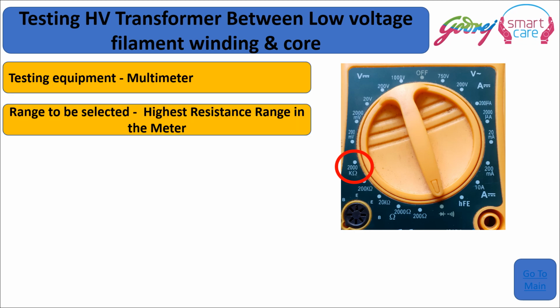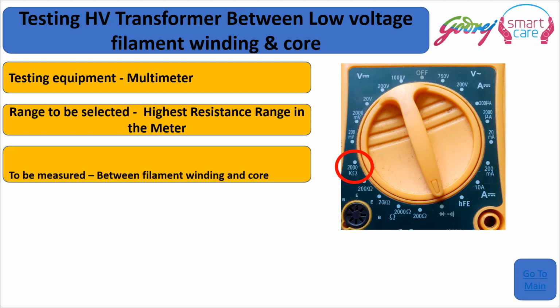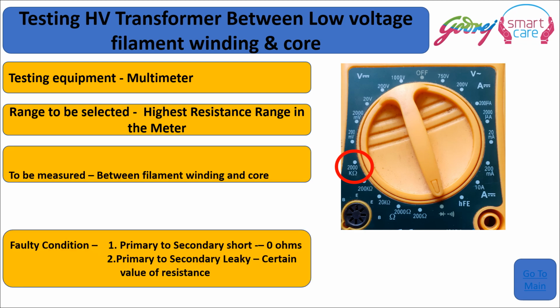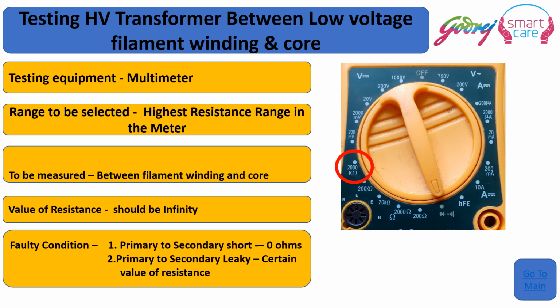Checking between the filament winding and the core, again set the multimeter to the highest resistance value. Between the filament winding and the core, short is 0 ohms, leaky is a certain value of resistance. And actually it should be infinity to indicate that it is a good transformer.